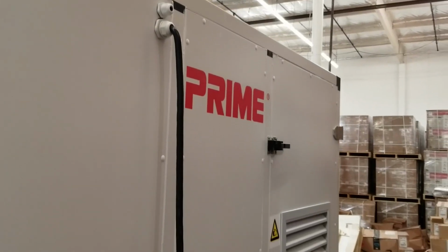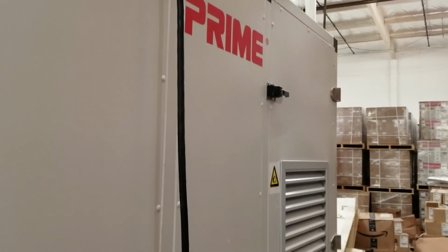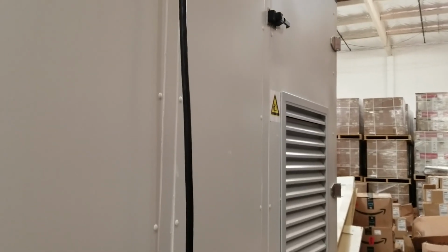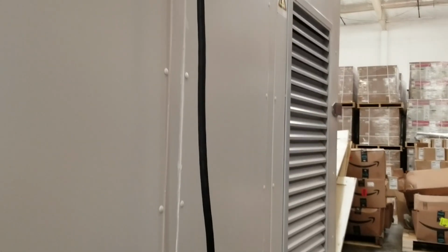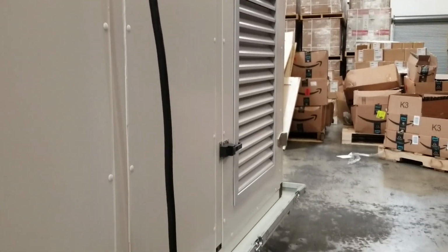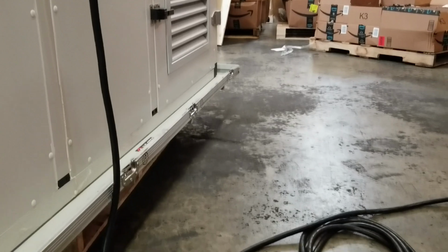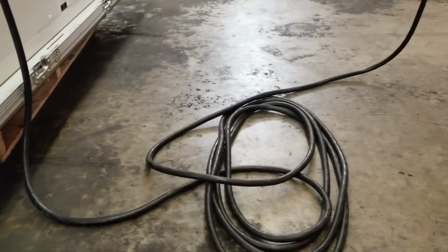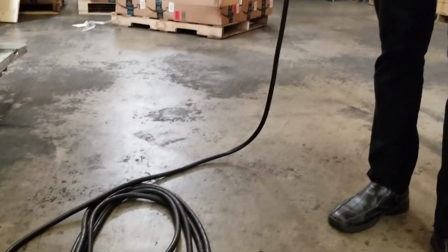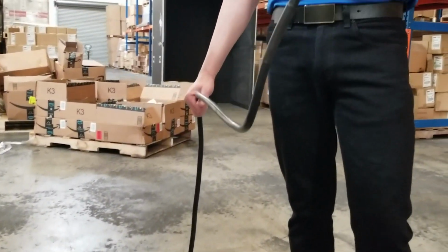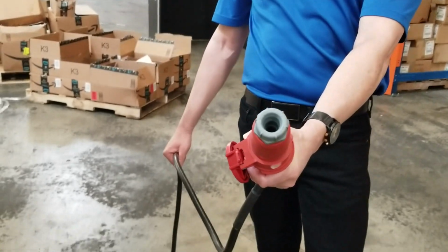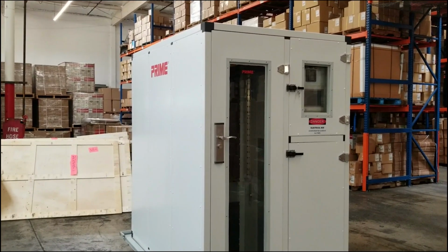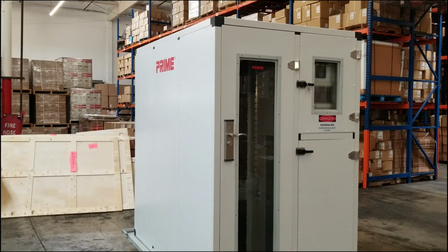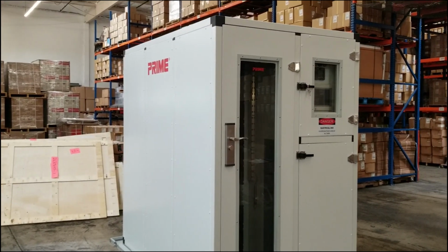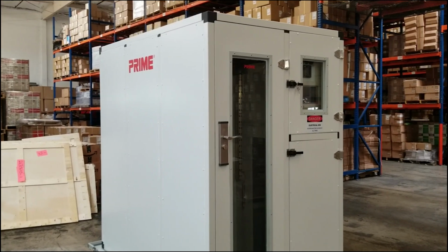When we say plug and play, we also mean that each MDC comes with a pre-wired, super heavy-duty 10-gauge 600-volt, extreme temperature-rated, oil, water, and abrasion-resistant, flame-retardant Prime power cable. We also include 4 SC fiber optic connections per rack for incoming and outgoing high-speed data transmission. Adding to the plug-and-play convenience is the fact that for the 1 and 2 rack units, you only need a standard industrial-grade forklift to bring the MDC to its location once it's been delivered to the site.